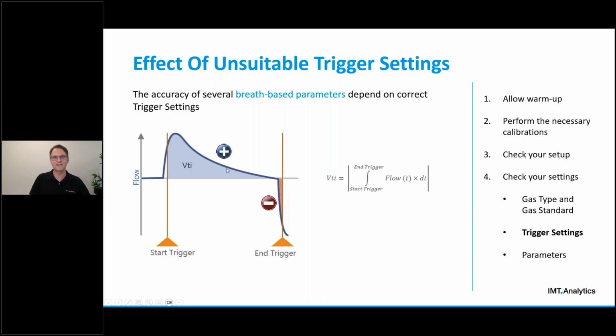And as you can see in this graphic here, these triggers are a little bit delayed, and this will have an impact on our tidal volume calculation, because a little portion here at the start of the inspiration is being lost, because our trigger is too late. And afterwards, after the inspiration phase, because our end trigger is too late as well, a little portion of our exhalation is being considered as negative volume deducted from the calculated VTI. So that means our calculated VTI by our gas flow analyzer in this example will be significantly too low.